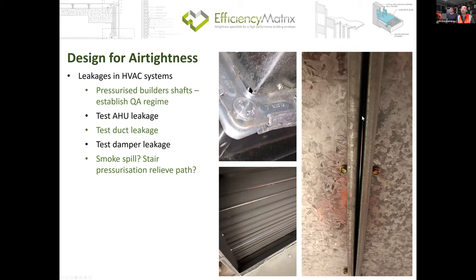And then another thing we need to consider is if you have a pressurized builder's shaft as your supply or return air path, make sure you establish a regime for quality assurance, especially the walls that will be encased inside the riser. Those are very easily overlooked and very, very, very difficult and expensive if you try to rectify that.